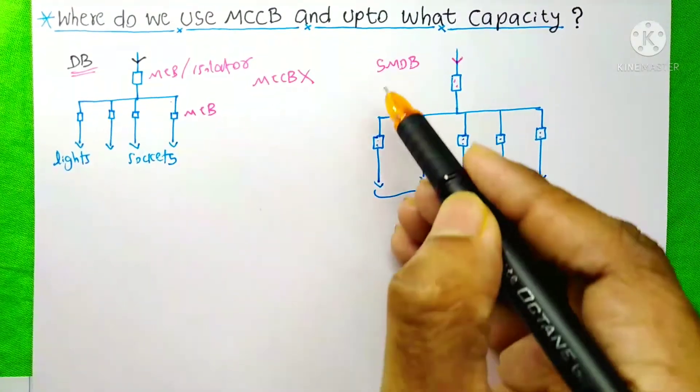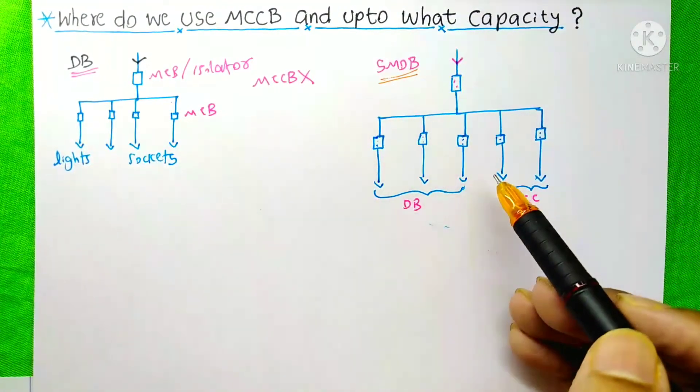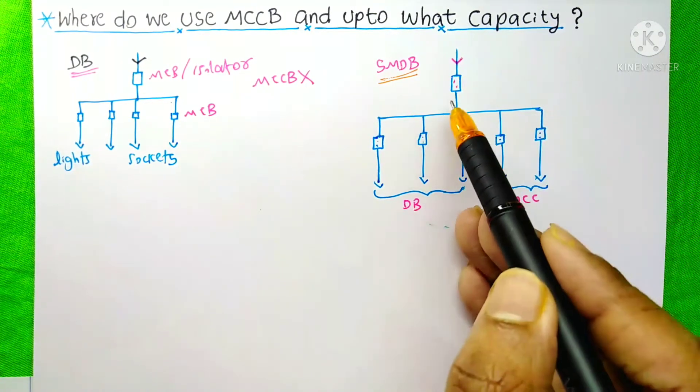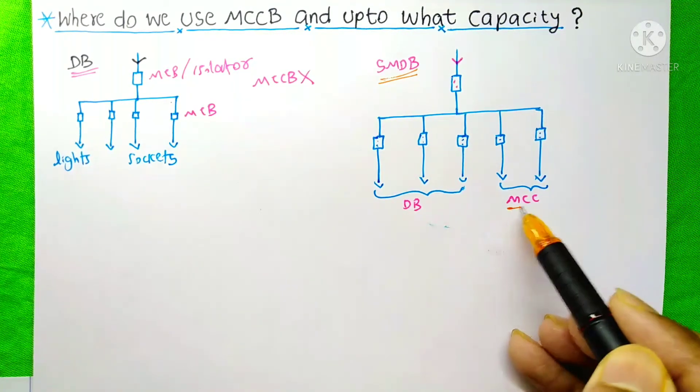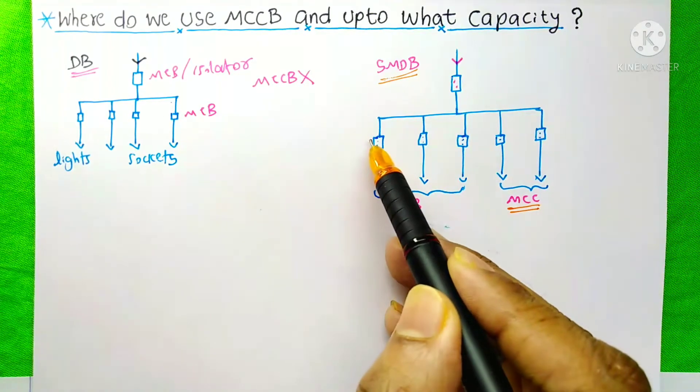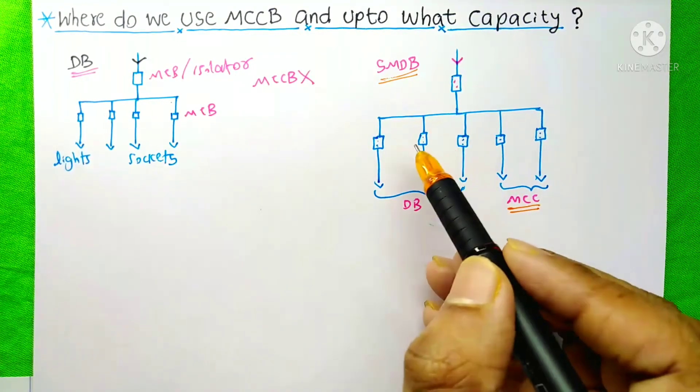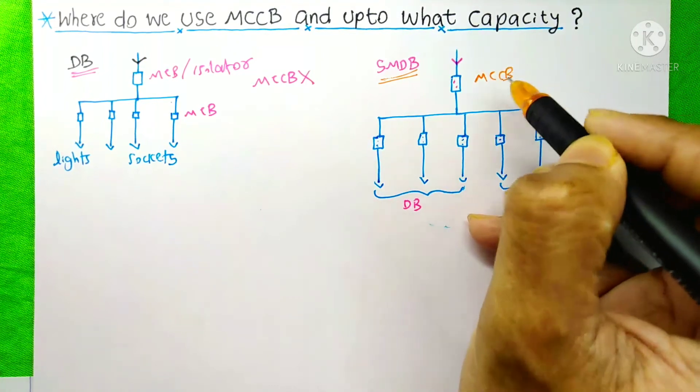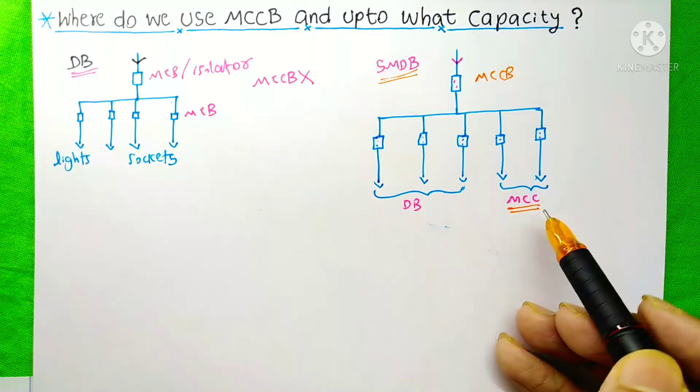The next case is about the SMDB. It is an SMDB and it is the main breaker of this SMDB. And this SMDB is feeding different DBs and also the MCCs that is Motor Control Centers. And these are the branch breakers for these DBs and MCCs. Generally for this SMDB, we use MCCB for the incoming breaker. And for the DBs and MCCs also, we use MCCB.